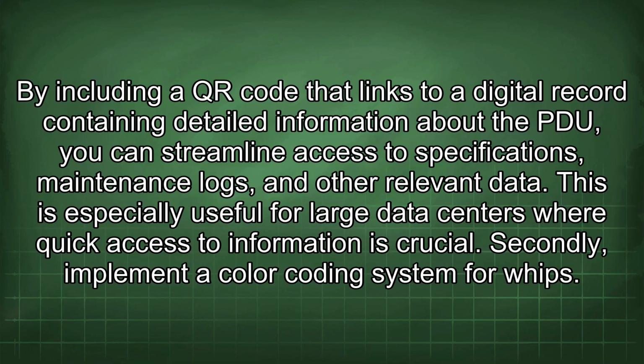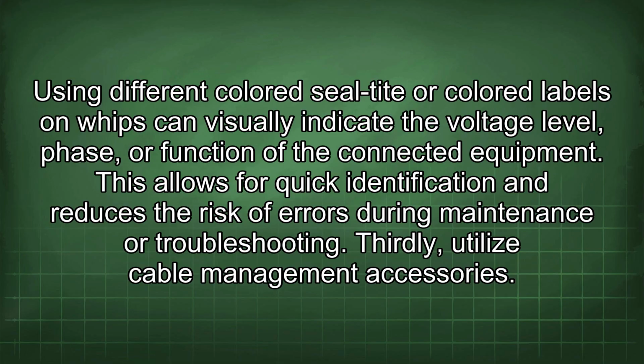Secondly, implement a color coding system for whips. Using different colored Seal-Tite or colored labels on whips can visually indicate the voltage level, phase, or function of the connected equipment. This allows for quick identification and reduces the risk of errors during maintenance or troubleshooting.